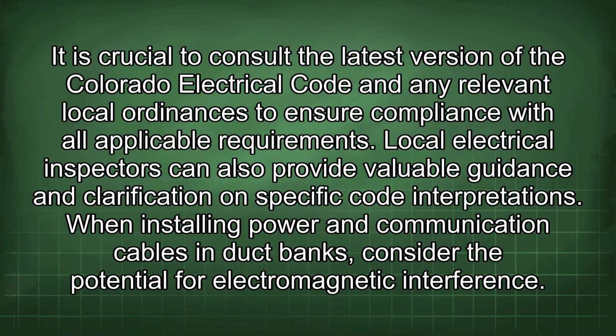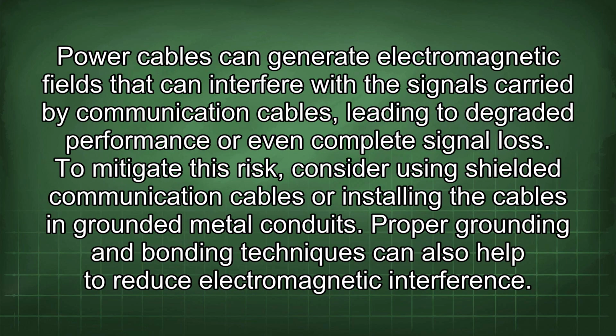When installing power and communication cables in duct banks, consider the potential for electromagnetic interference. Power cables can generate electromagnetic fields that can interfere with the signals carried by communication cables, leading to degraded performance or even complete signal loss. To mitigate this risk, consider using shielded communication cables or installing the cables in grounded metal conduits. Proper grounding and bonding techniques can also help to reduce electromagnetic interference.